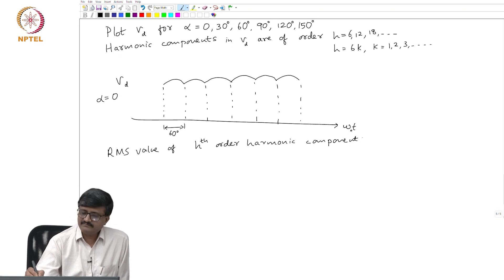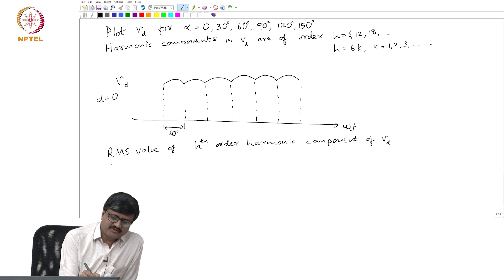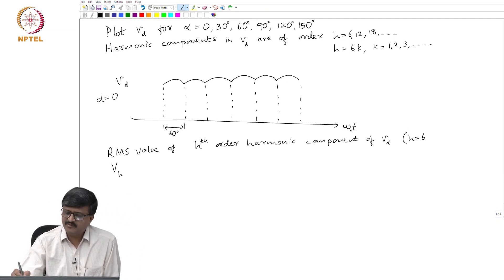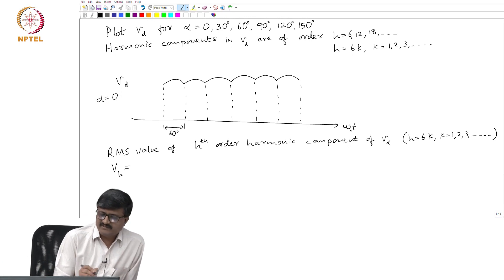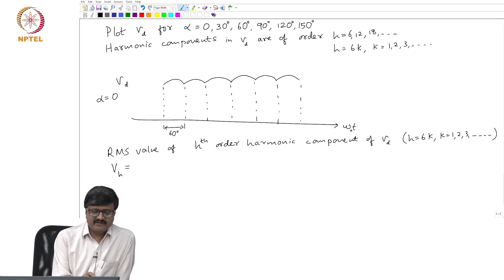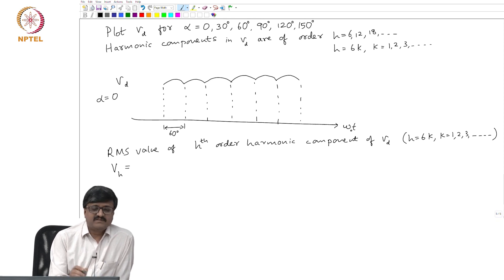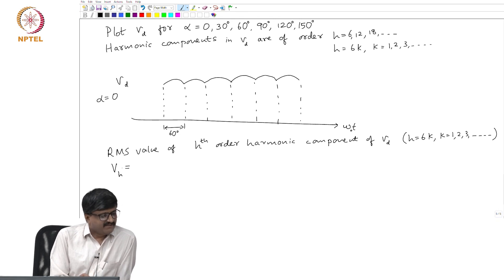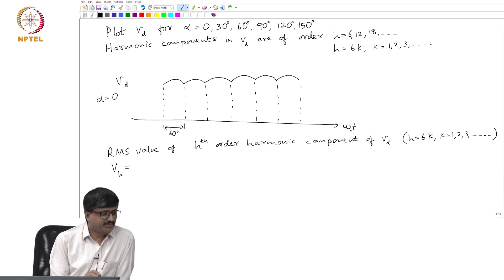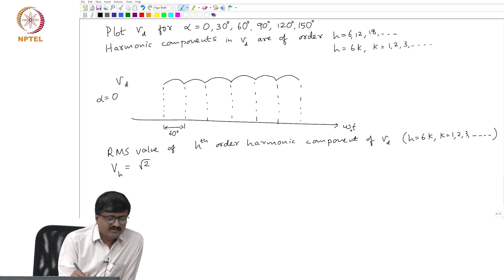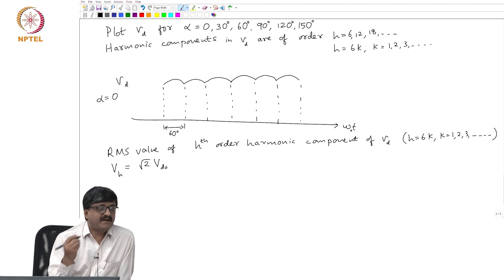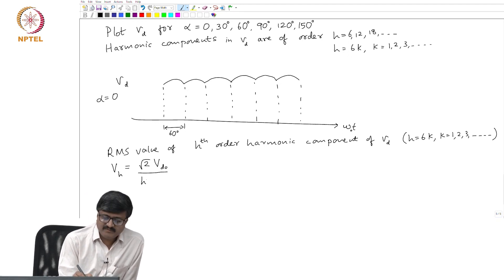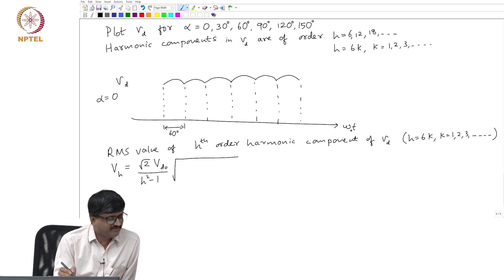The RMS value of the hth order harmonic component of V_D — I will use the notation V_h. Please note: h equals 6k where k is 1, 2, 3, and so on. For these values of h the harmonic component has an RMS value V_h, where uppercase V with subscript h denotes the RMS value. We know how to use Fourier series; I will give the answer and leave the derivation to you. The expression is: V_h = √2 · V_D0 divided by (h² − 1) multiplied by √(1 + (h² − 1)sin²α), where V_D0 is the maximum average DC voltage.